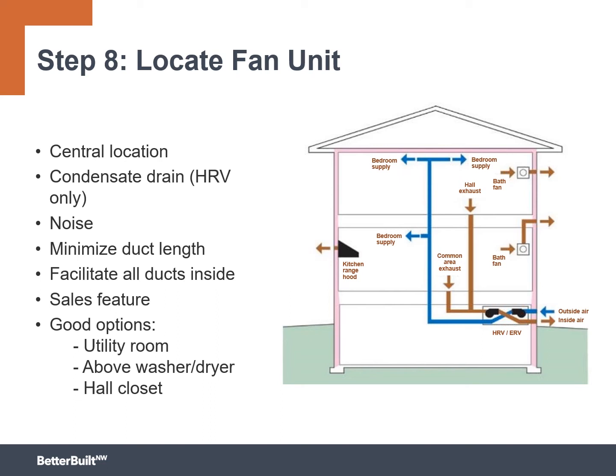You want to think about noise, probably not in the master bedroom closet, for instance. Again, any opportunity to minimize our duct length will be a good thing for our static pressures. It helps make sure we get the flow we want. We want to make sure we can facilitate getting all of our ductwork inside of our thermal envelope, meaning inside of the insulation and air barrier of the home.